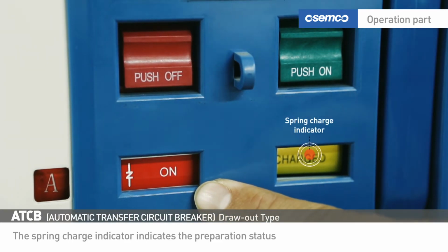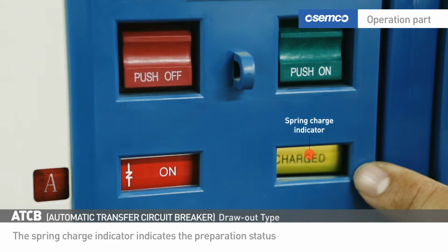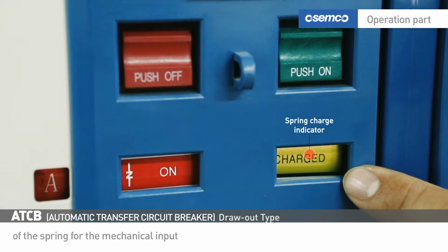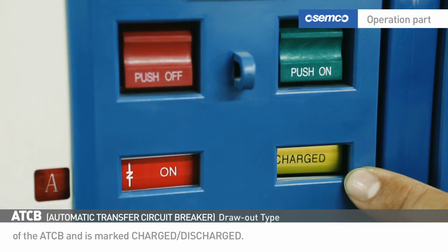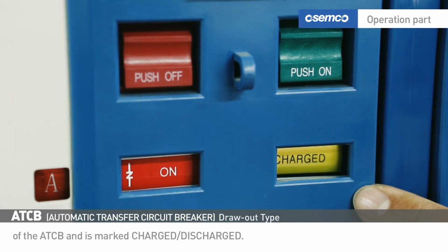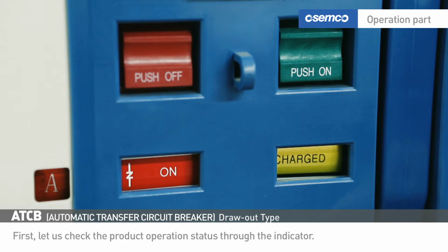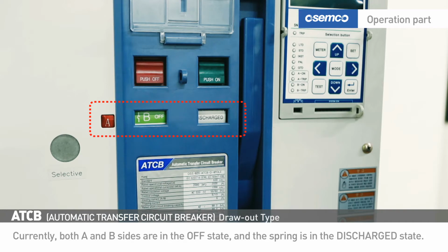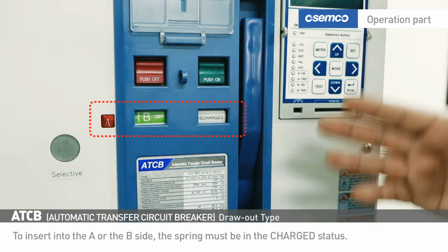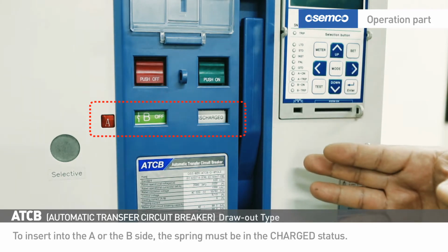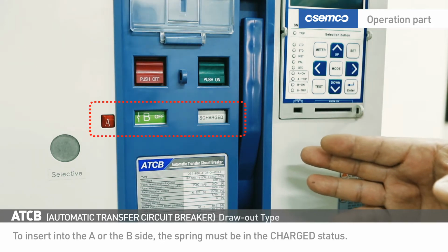The spring charge indicator indicates the preparation status of the spring for the mechanical input of the ATCB and is marked charged, discharged. First, let us check the product operation status through the indicator. Currently, both A and B sides are in the off state, and the spring is in the discharged state. To insert into the A or the B side, the spring must be in the charged status.